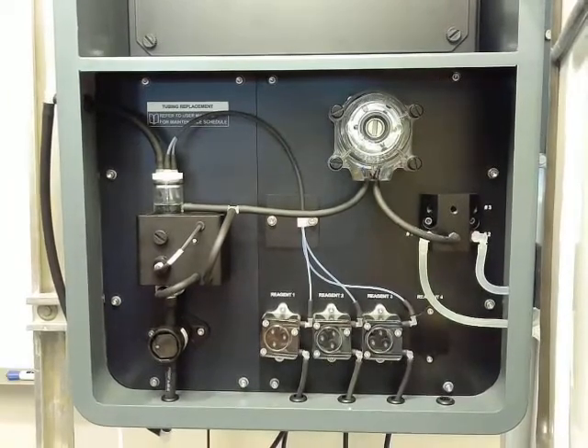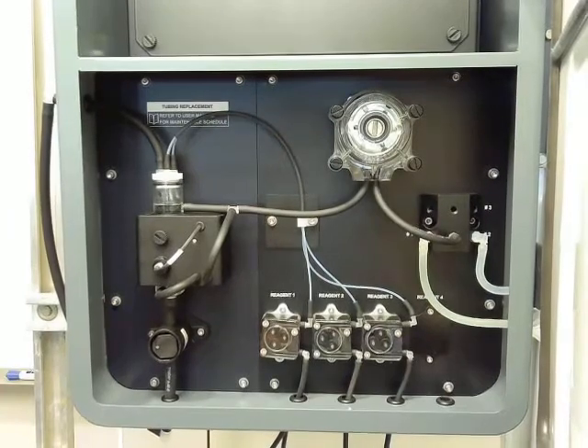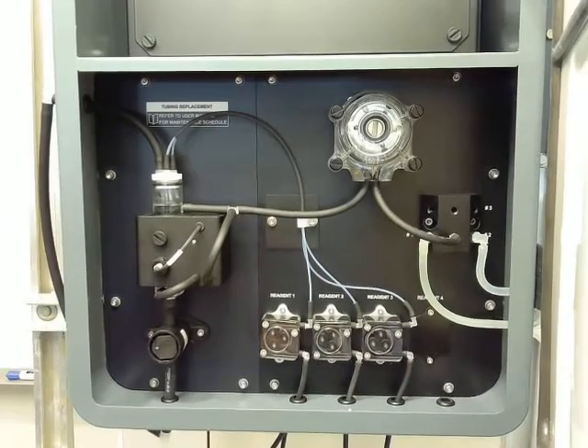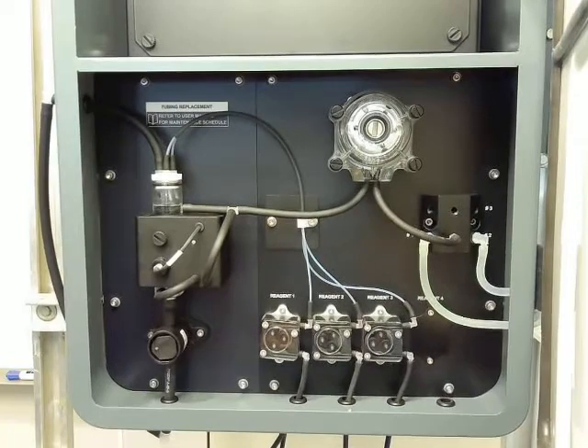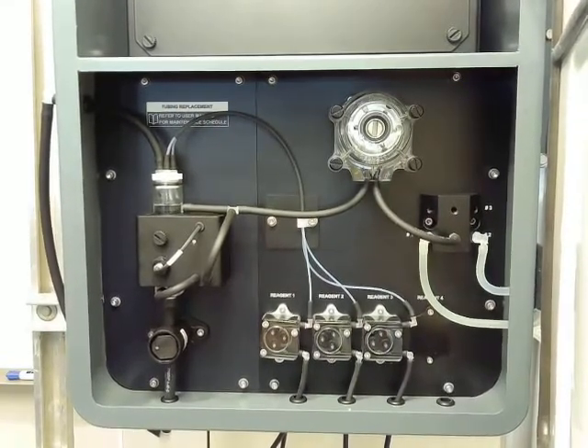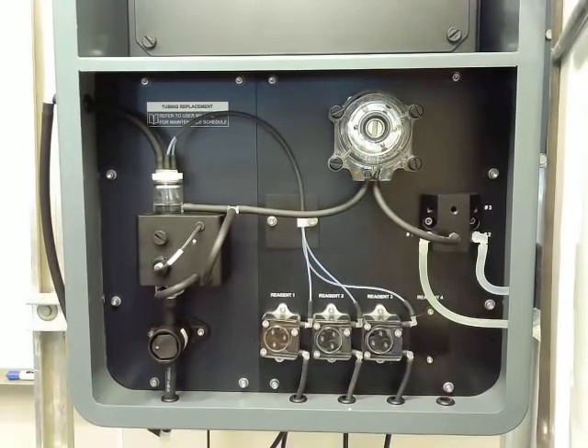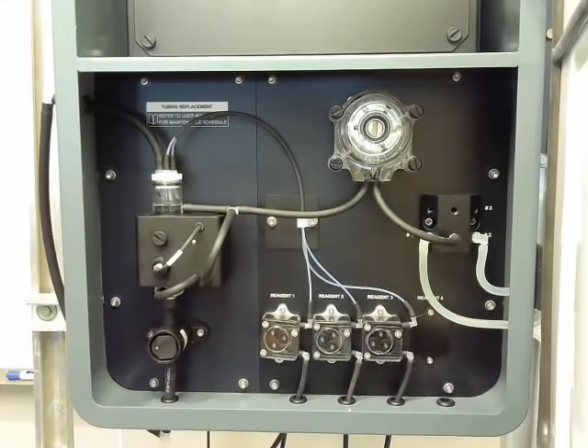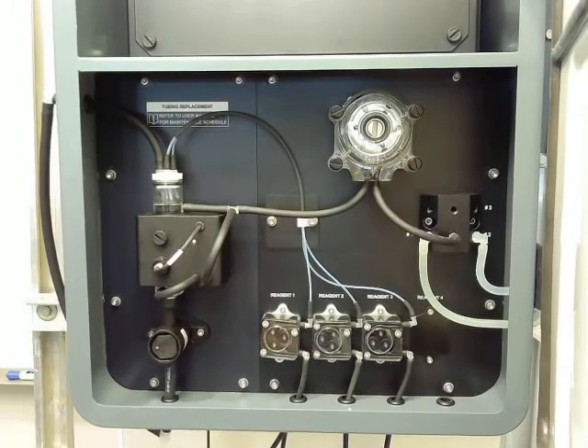But again, once that's in place, we'll have to go back and we'll do a reagents prime for 60 seconds to make sure our reagent is primed through all these tubes. So it's a good idea to line this up with a reagent replacement, since you're going to have to prime your reagent lines anyway. Then it's always a good idea to run a cal after you do this too. Make sure everything's working correctly, and make sure that analyzers can be accurate when it goes back online. So that's all the quarterly tubing replacements. Any questions on that, or want to see any of them again or closer?